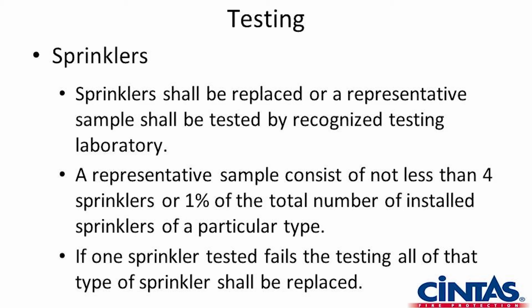Quick response sprinklers came into existence in the late 80s, early 90s. At a 20-year interval, those sprinklers have to undergo that testing that we just spoke about with a 50-year-old head, but their frequency is much less. Now we're talking about 20 years. So if we've got a facility that is greater than 20 years old and it has quick response or fast response sprinklers in it, then we are seeing more and more, because that 20 years just has really started kicking in in the last few years.